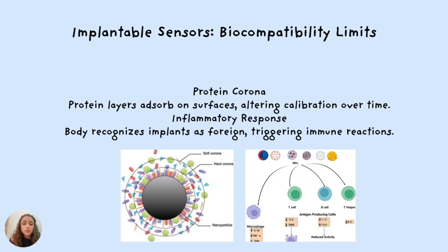The challenge is long term biocompatibility. Implanted sensors need to function reliably for months or years without triggering inflammation. Plus, the protein corona, layers of proteins that coat device surfaces, can alter sensor calibration over time. Most implantable systems currently need periodic maintenance or replacement.